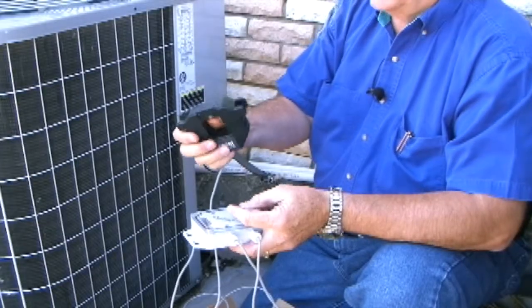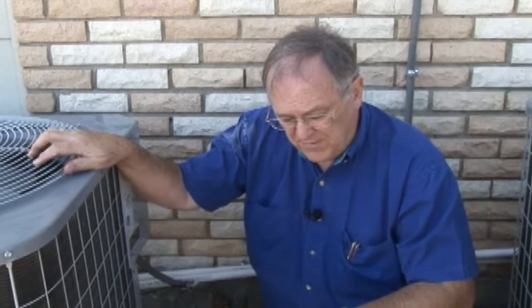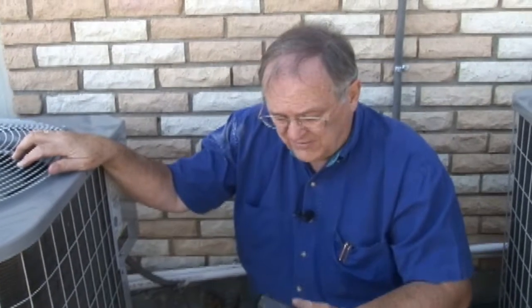Let's talk about installing a data logger on a typical DX split system where the condenser is totally separate from the air handling unit. In this case, we're going to have to install a separate data logger to pick up the current that the system is using. And we'll have to have a number 2 data logger inside on the air handling system so we can put the temperature sensors in the airstream of the return air and the supply air. This is very simple to do.